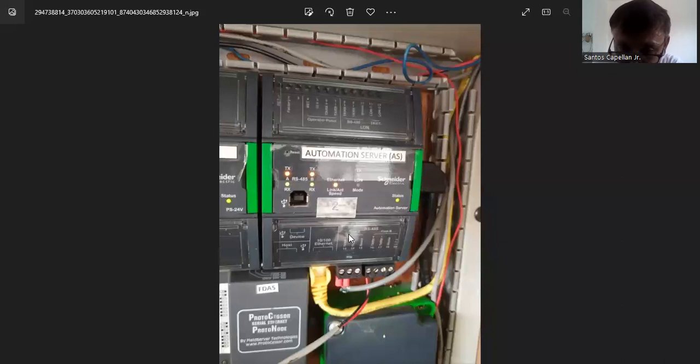I'm using COM-A for this one. As you can see, I have a two core cable here. I use this for my BACnet controllers. Now, from that BACnet interface, I created another MSTP network using communication port B. This time, I'm dedicating this for my VAV boxes.